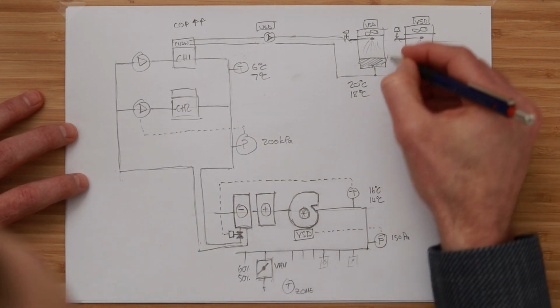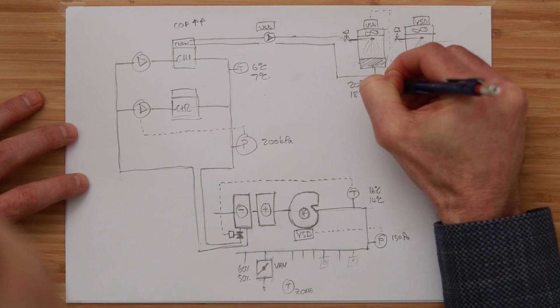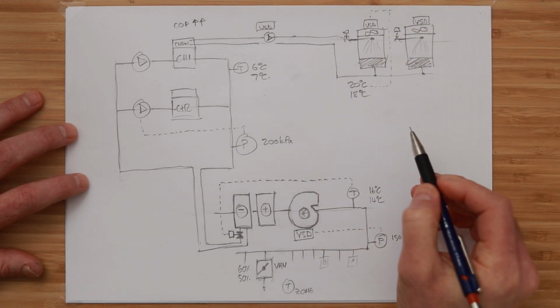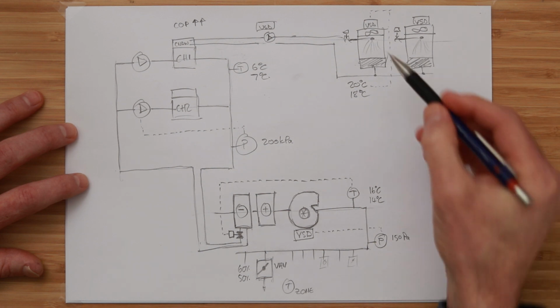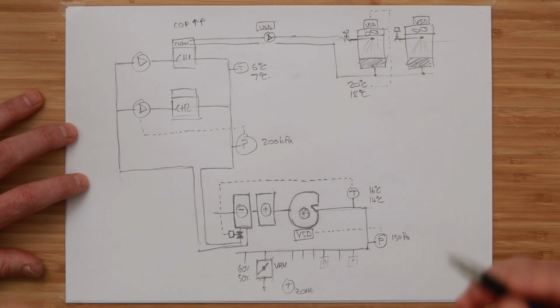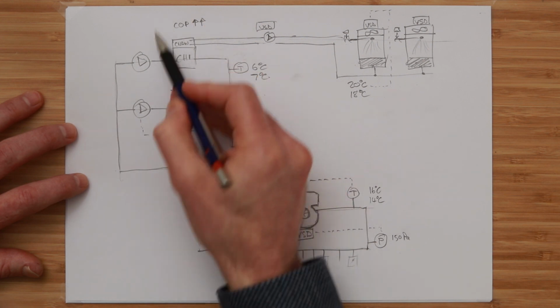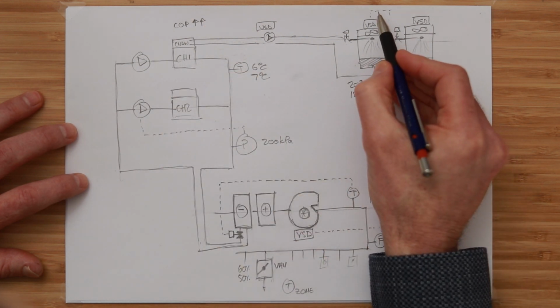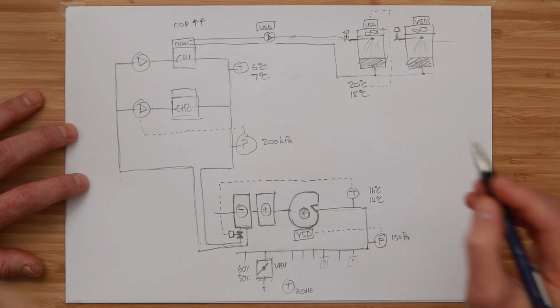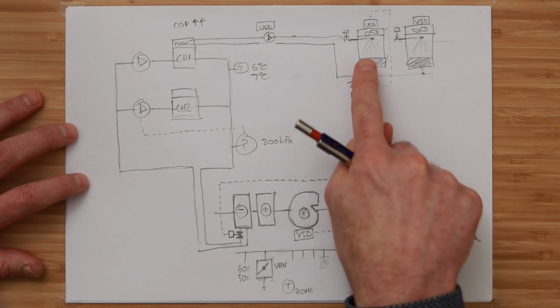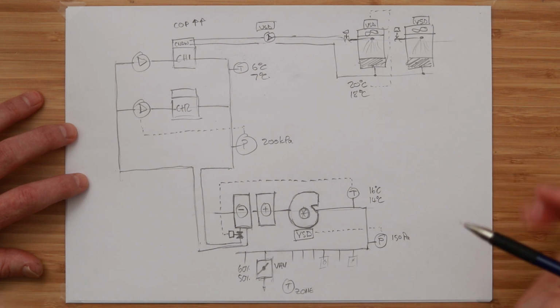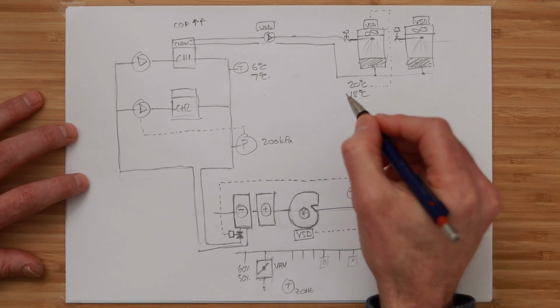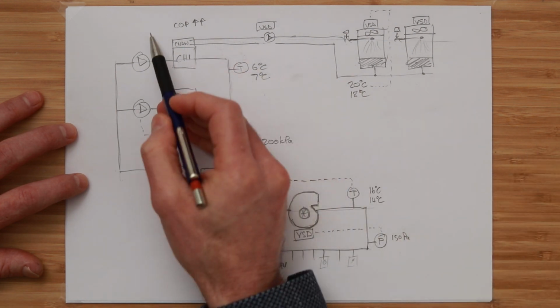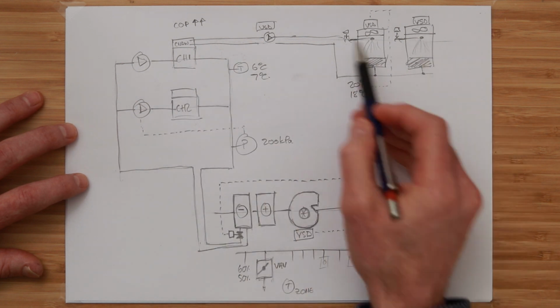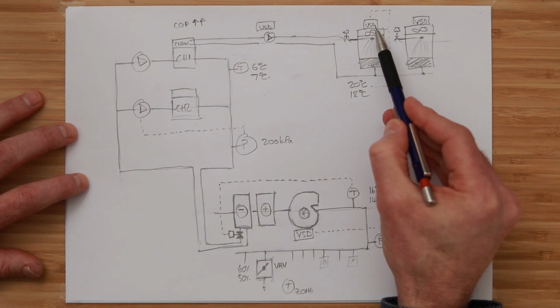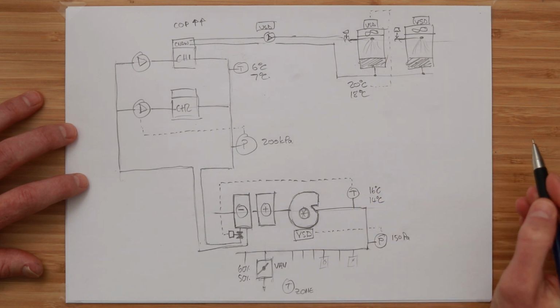But obviously, as you reduce the condenser water temperature to make the chiller more energy efficient, we have to run the cooling tower fans harder. So as we're seeing improvements here in our optimization, we're drawing more power through our fans here. I think there's been videos last year where we've discussed this circuit and this circuit, how these two optimization strategies work. But the point being, again, we're optimizing something here, and on the roof plant room, we're not noticing that the fans are running harder to achieve that optimization strategy.